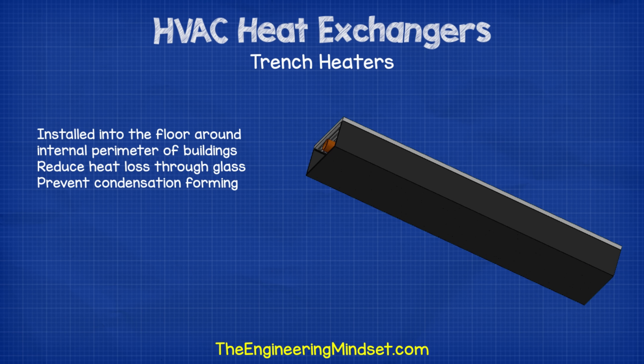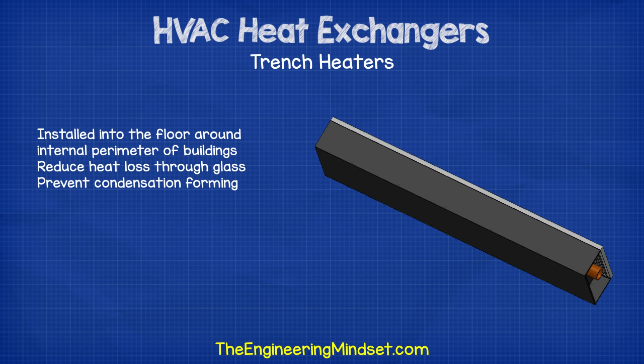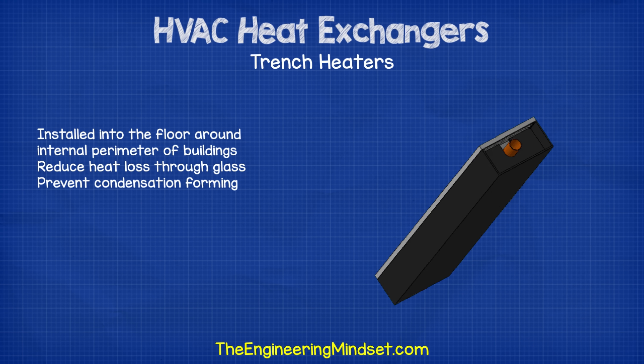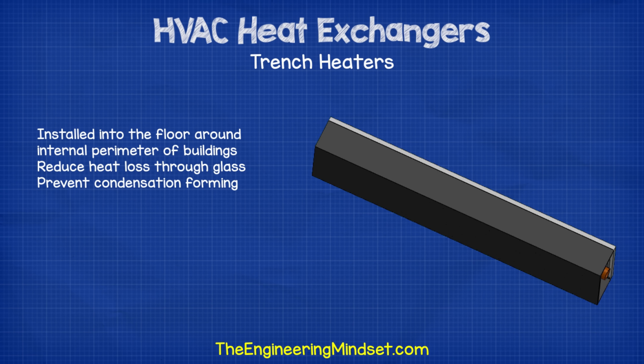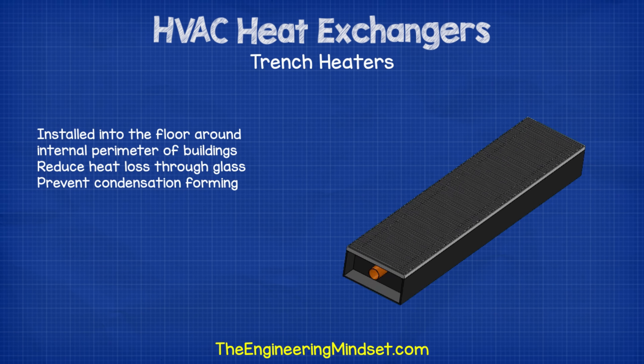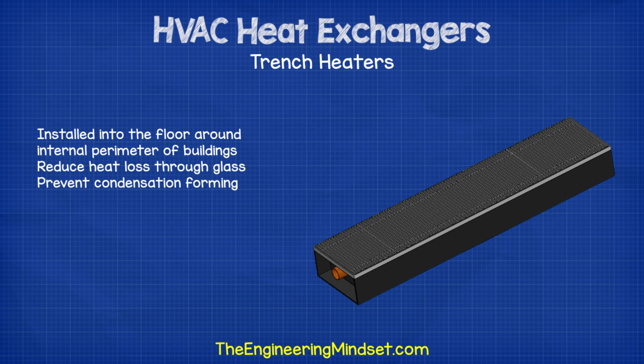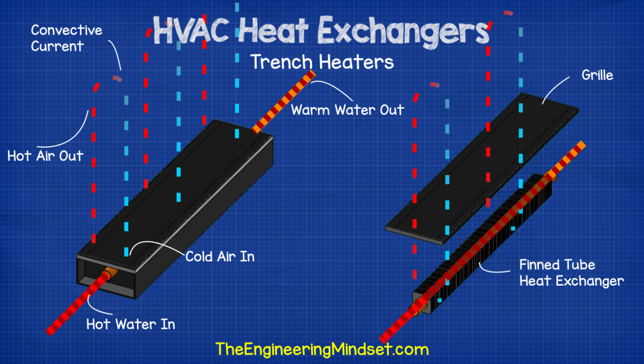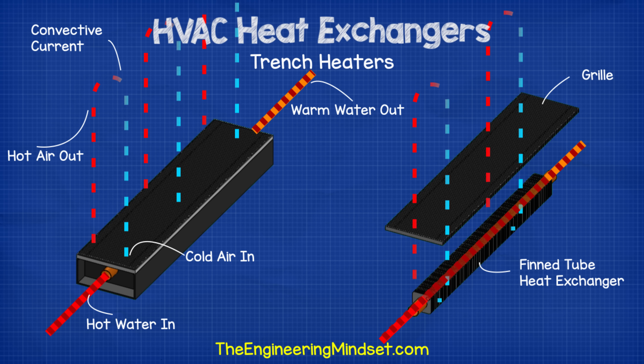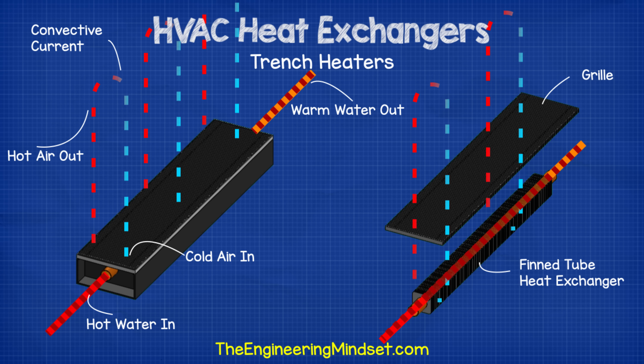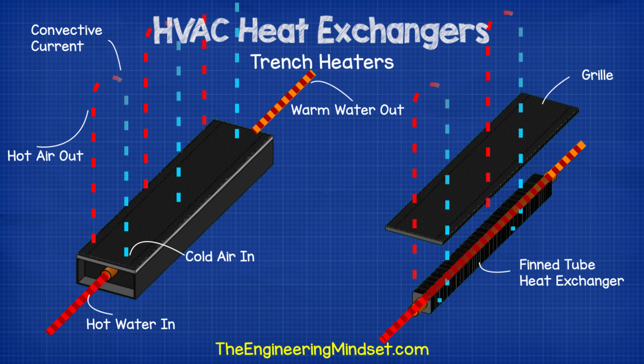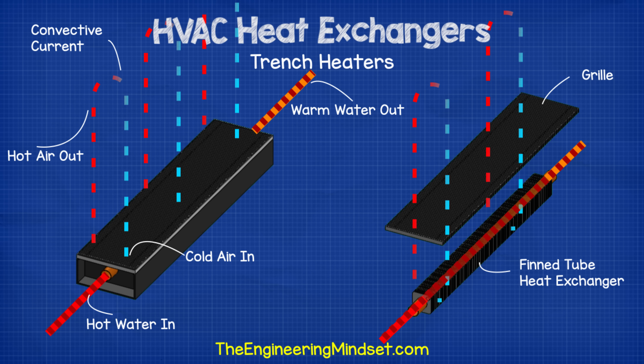Trench heaters are installed around the perimeter of a building, usually under a window or glass wall, and are very common in new commercial buildings. They are installed into the floor to reduce heat loss through the glass and prevent condensation forming by creating a wall of convecting air currents. Trench heaters use hot water or electric heating elements. Their position at floor level gives access to the coldest air in the room. The heat exchanger heats this cold air, causing it to rise, and cold air rushes in to replace it, creating a continuous convective current.